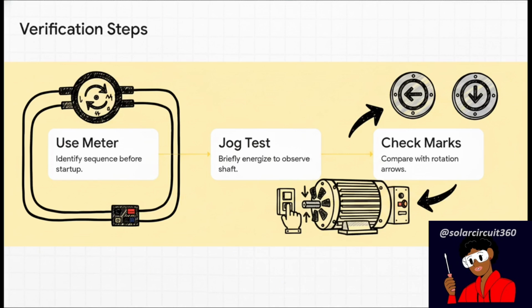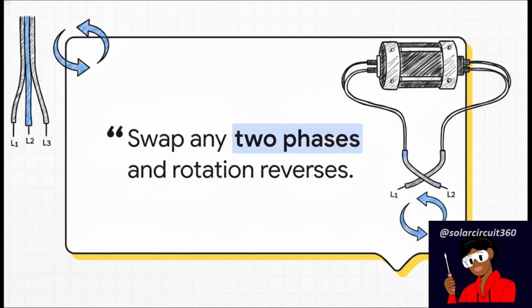power to the motor. Step 2, assuming it's permitted and safe, is the motor jog test. This just involves briefly energizing the motor for a tiny fraction of a second, literally just enough to bump the shaft, so you can visually observe which way the fan blade or coupling is spinning. And finally, step 3 is validating what you found against mechanical indicators. Almost all industrial equipment is going to have rotation arrows, direction markings, or flow indicators stamped right onto the metal housing. If your jog test shows it's spinning clockwise, but the stamped arrow is pointing counterclockwise, well, you've got a phase rotation error.